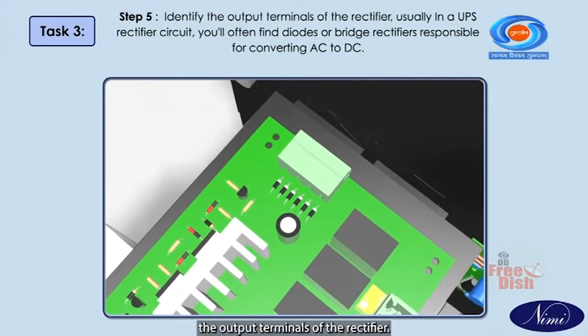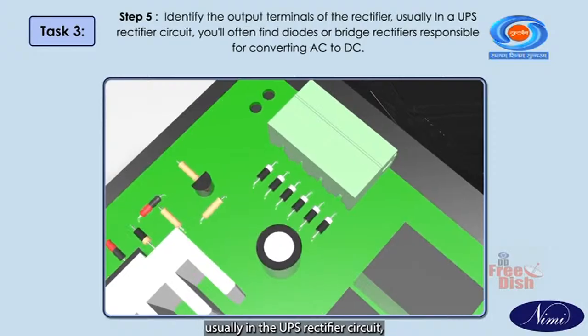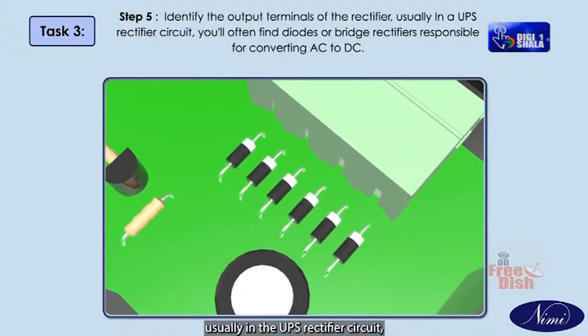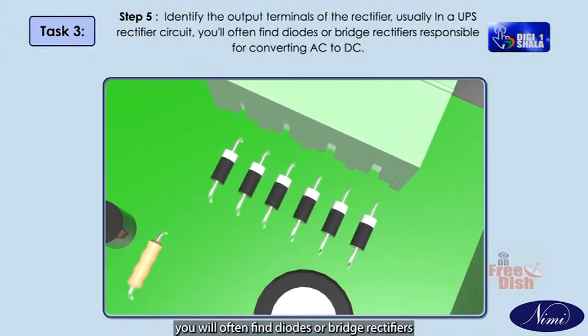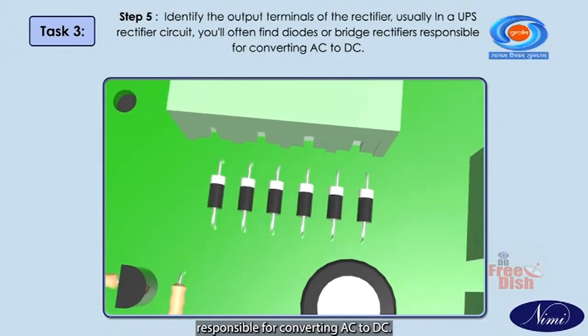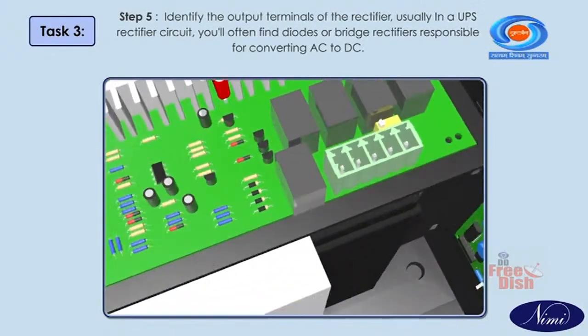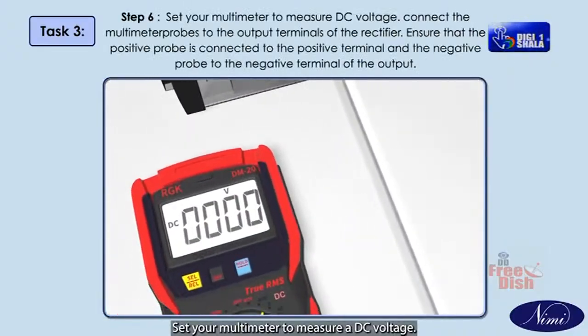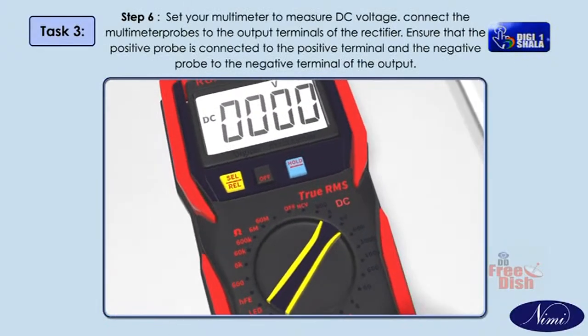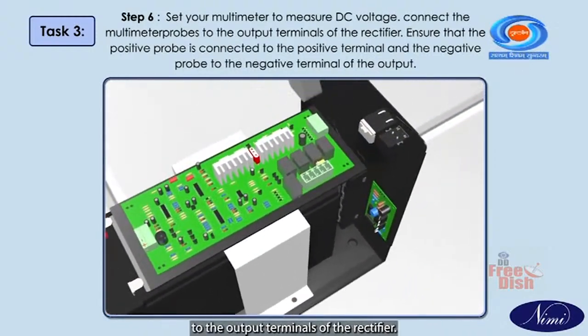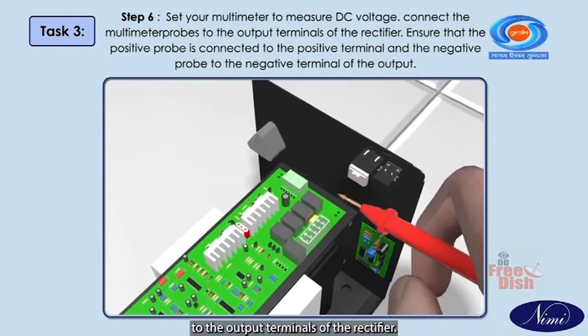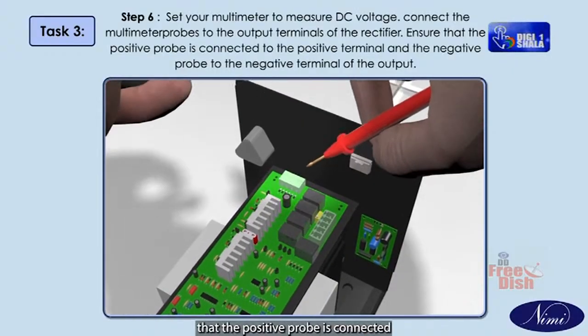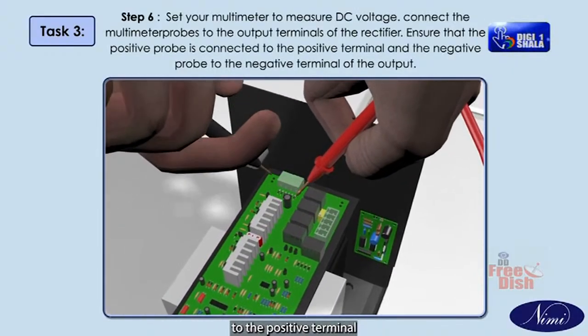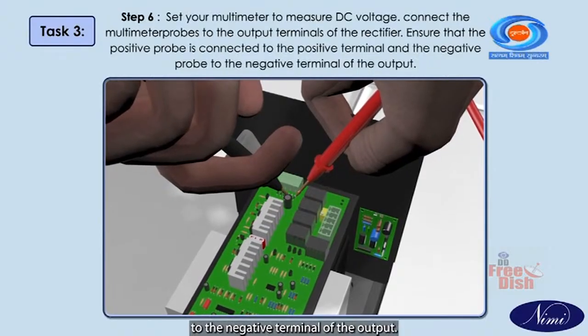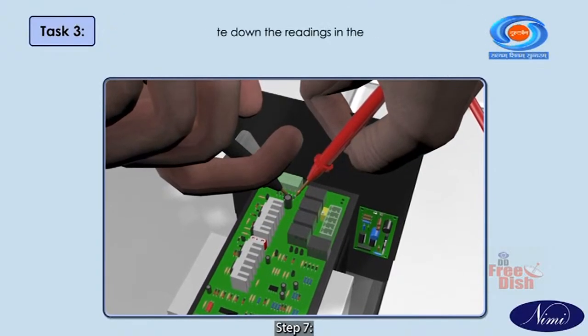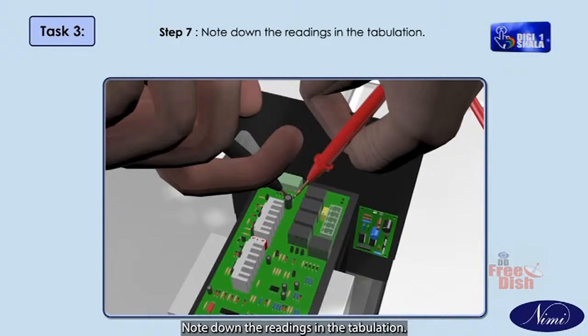Step 5. Identify the output terminals of the rectifier. Usually, in a UPS rectifier circuit, you'll often find diodes or bridge rectifiers responsible for converting AC to DC. Step 6. Set your multimeter to measure DC voltage. Connect the multimeter probes to the output terminals of the rectifier. Ensure that the positive probe is connected to the positive terminal and the negative probe to the negative terminal of the output. Step 7. Note down the readings in the tabulation.